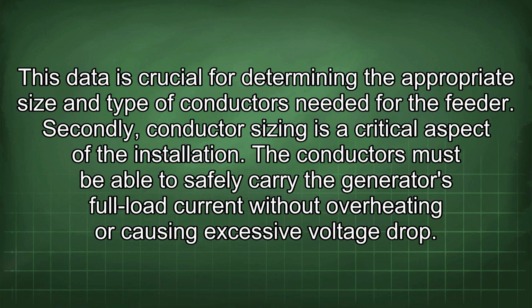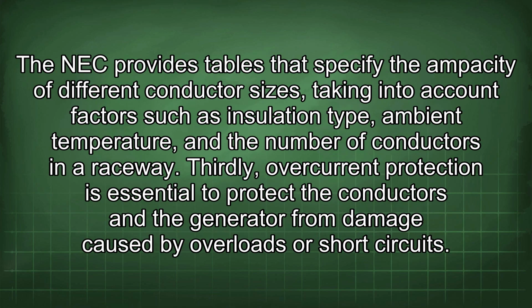Secondly, conductor sizing is a critical aspect of the installation. The conductors must be able to safely carry the generator's full load current without overheating or causing excessive voltage drop. The NEC provides tables that specify the ampacity of different conductor sizes, taking into account factors such as insulation type, ambient temperature, and the number of conductors in a raceway.